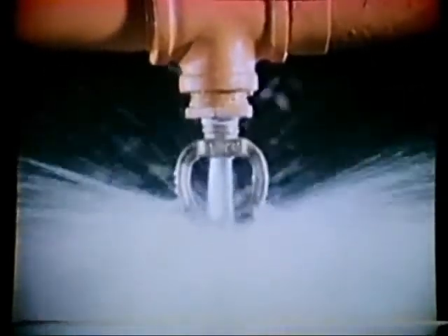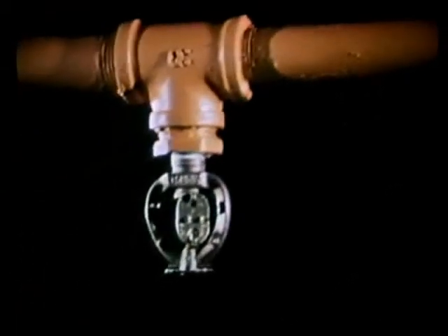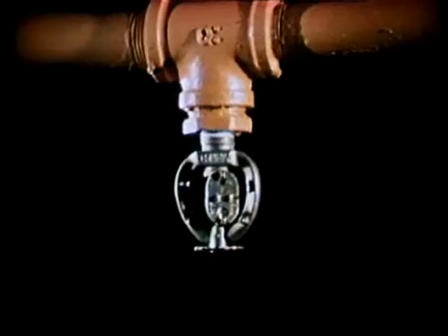The first method we'll consider for increasing the density is to change the temperature rating using a higher rated temperature head. This allows more concentration of water on the immediate fire area. It has been proven that if the temperature rating of the sprinkler is too low, heads outside of the fire area will fuse in a high heat release fire.